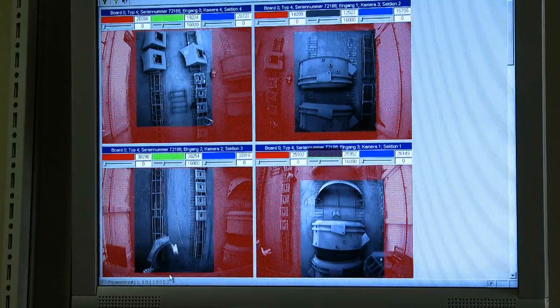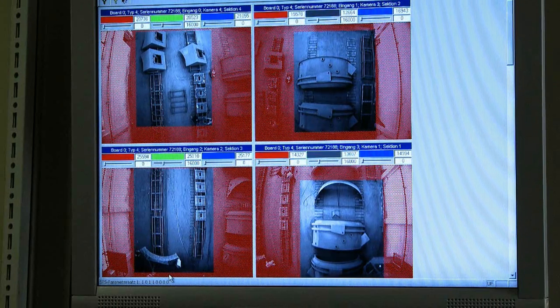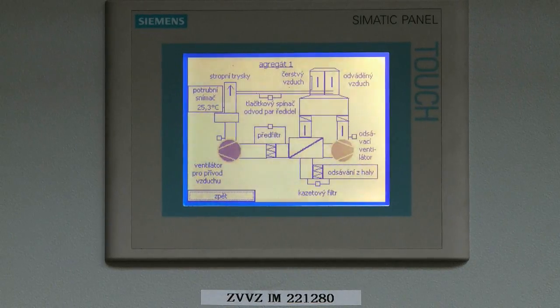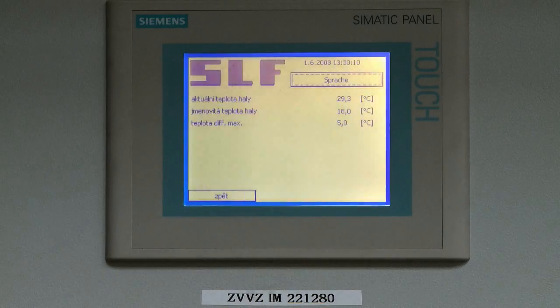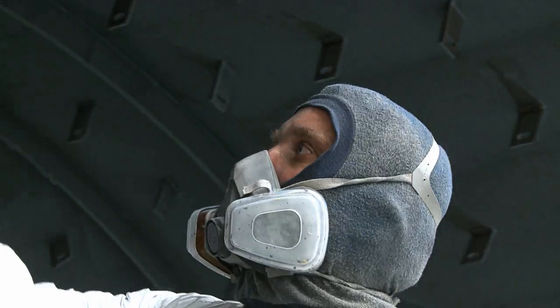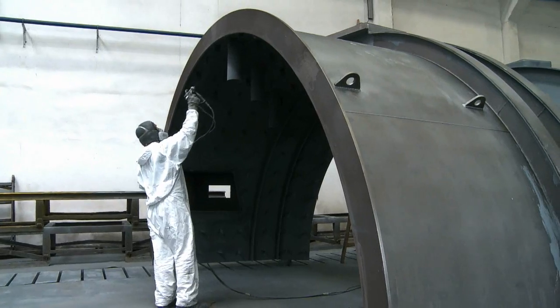Of course, the process of controlling a coating installation also includes the regulation of the hall's temperature. The control cabinet has diagrams, available in the desired language, that display the proper function of this feature. Even when outside temperatures fall as low as -10 degrees Celsius, the coating technician needs a stream of air with a temperature of at least +20 degrees Celsius.